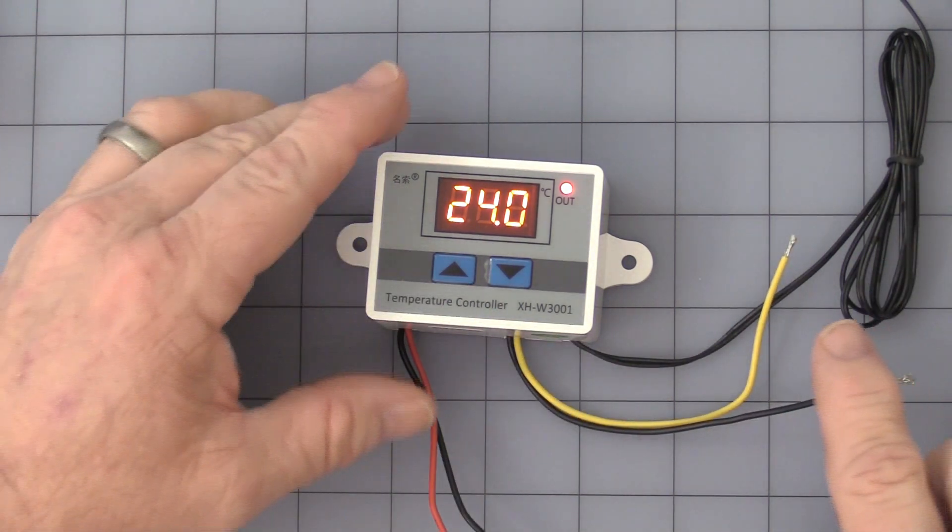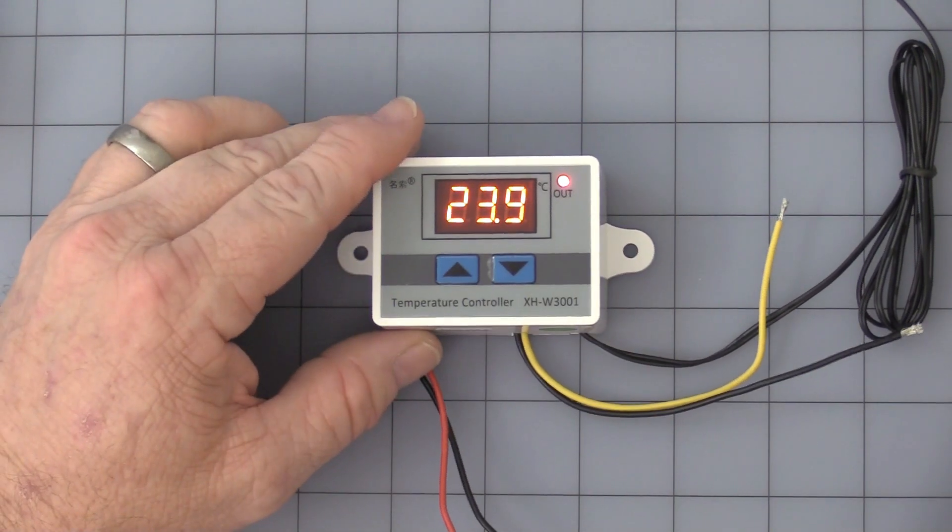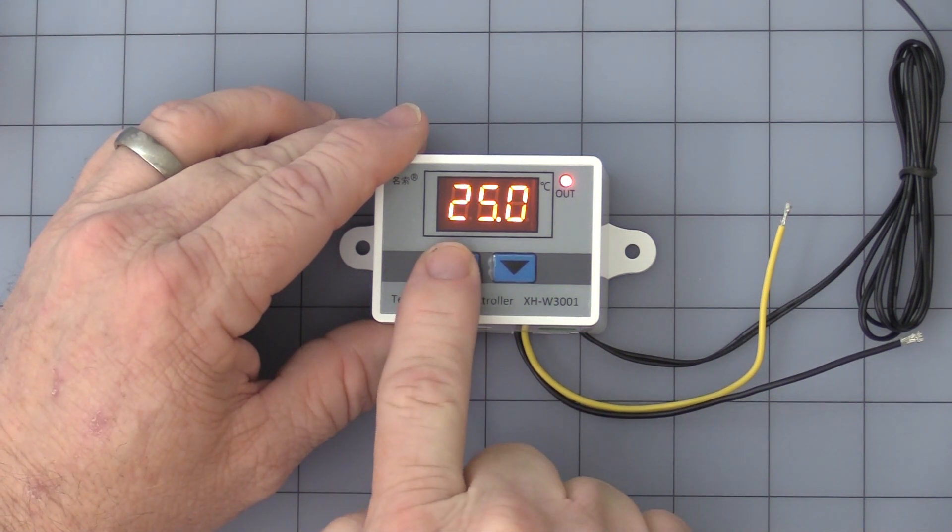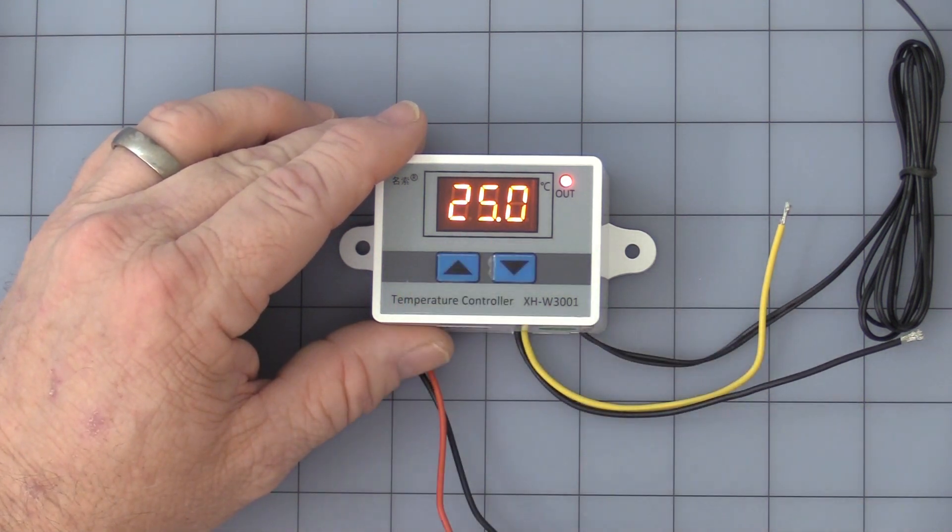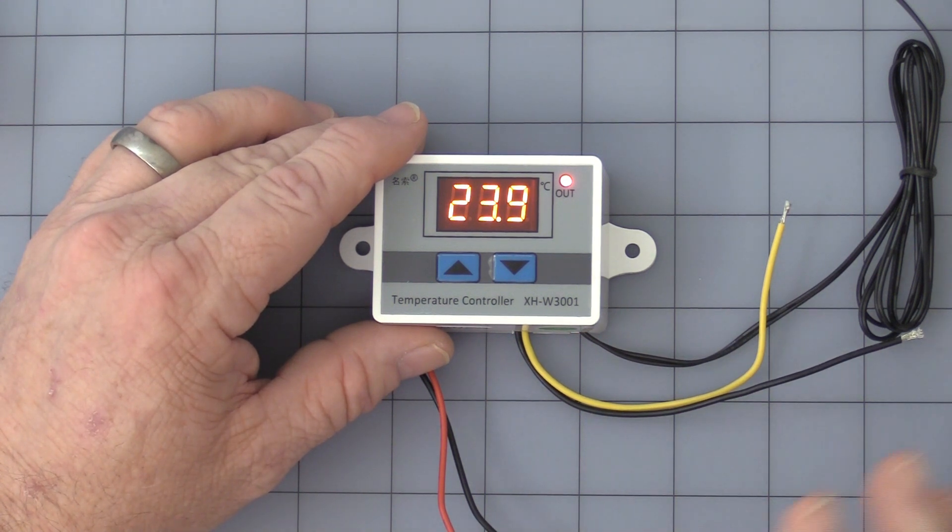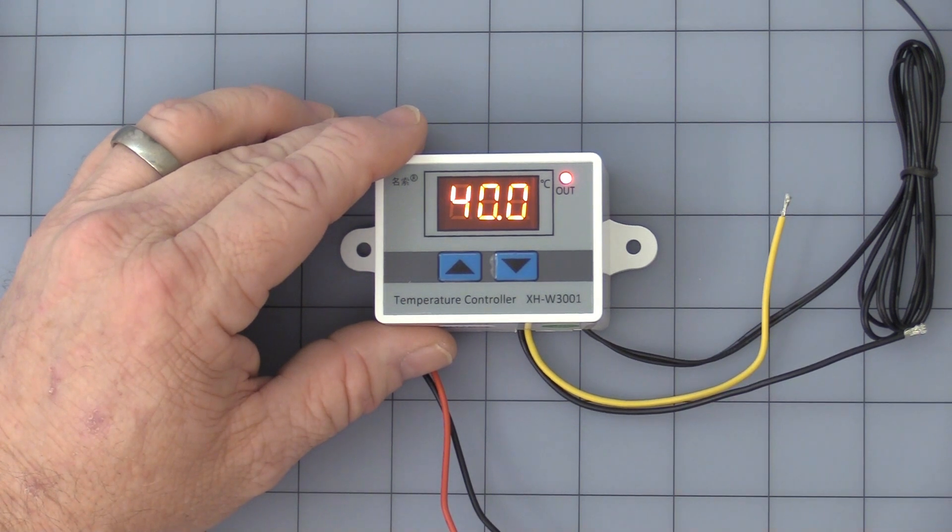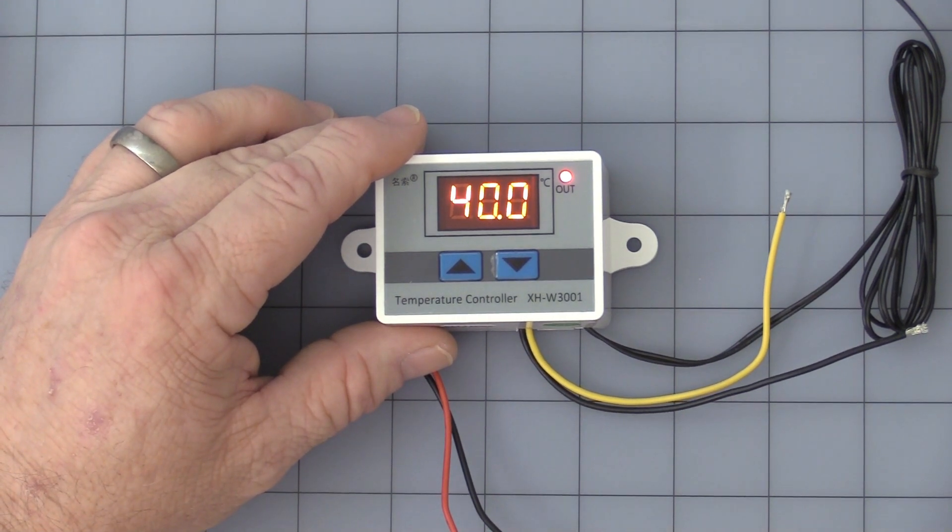Alright, let's get into some programming. To know where the set points are, you simply, on the up arrow you press, it comes factory set at 25 degrees Celsius. Leave it alone for a few seconds. It goes back to displaying air temperature. Press the down arrow. That is the other setting at 40, it comes factory set at 40 degrees Celsius.